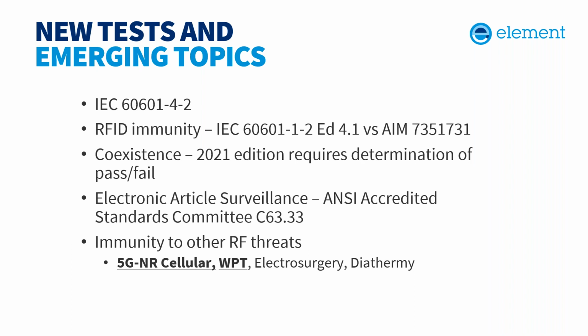Both of these radio technologies are becoming commonplace, and wireless power transfer from cell phones to electric vehicles is now in the field and could potentially affect medical devices. The FDA is asking for evaluation of these threats, but there are no published standards on testing for them. At Element, we've internally developed a test method to test the susceptibility of medical devices to these threats. So if you're interested in that, if you've got questions from the FDA, or if you need more information, please reach out.